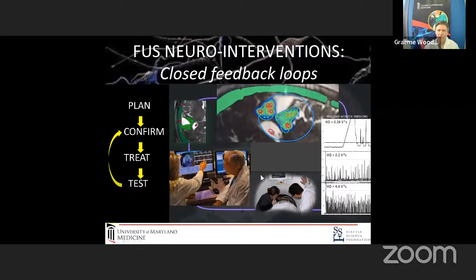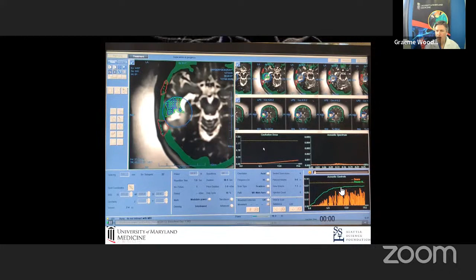So here's an example of what one of these treatments can look like while it's actually being performed. We have drawn a subspot grid around a resection cavity. We see the T2 weighted image here on the screen. The acoustic emission system and closed feedback loop system is driving over here. You have the power going in, the green line, and the energy coming out, the orange lines. And the system is rapidly cycling every millisecond to adjust the power to create the desired peak. And over time, what we see is the acoustic energy map develops in the field, and the system is actually delivering energy to a given dose that's prescribed by the provider prior to that treatment.